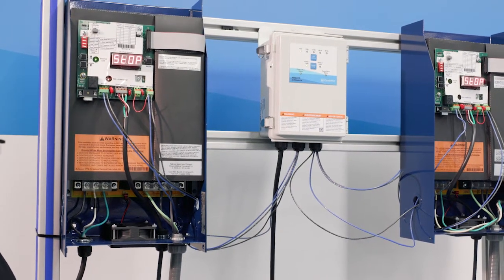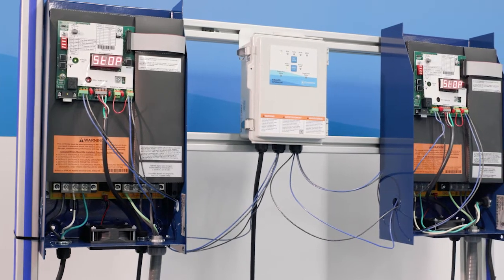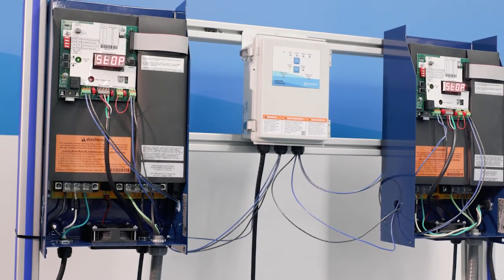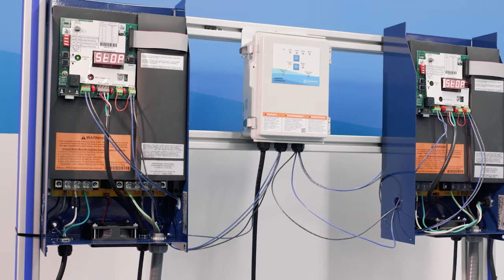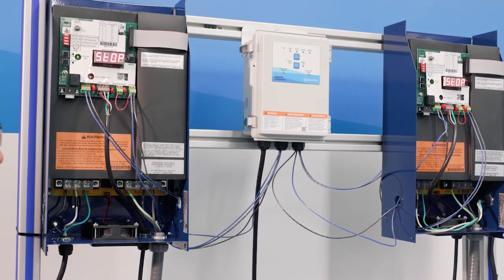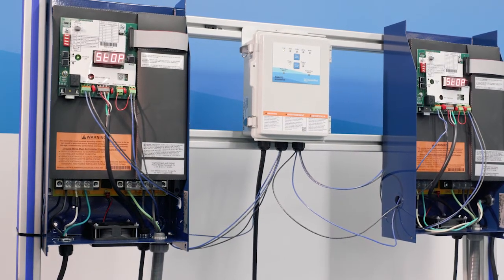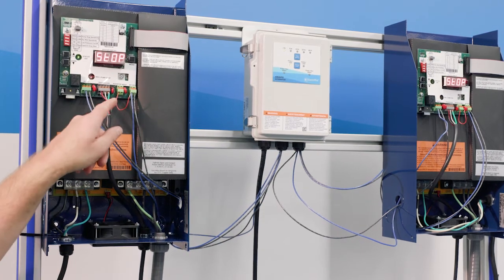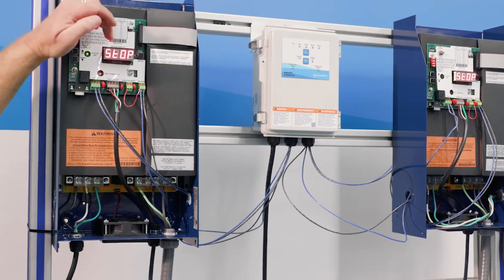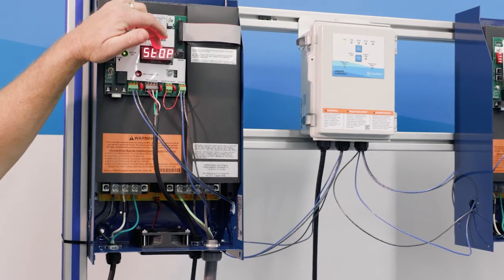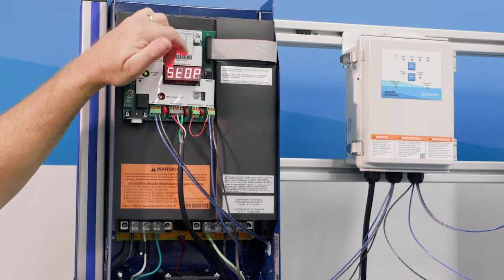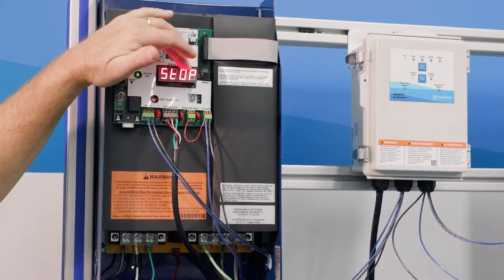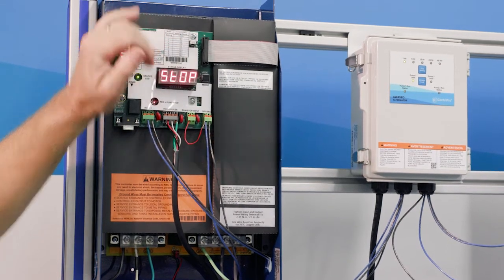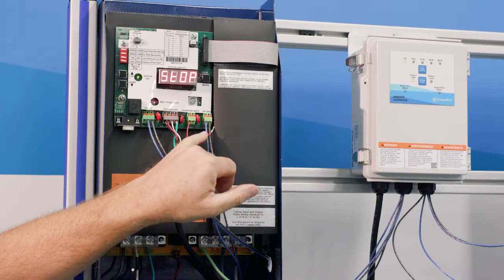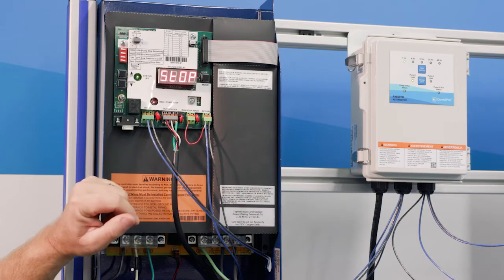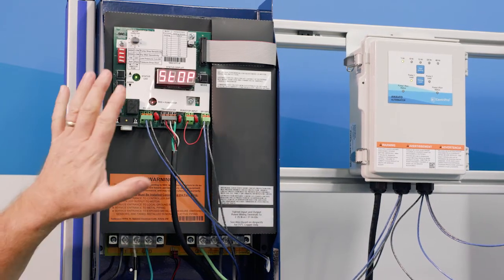We need to set the pressures up. And we basically need to set SP2, which is set pressure 2, and SP1, which is set pressure 1. So one of the tricks to do that is we got to have power to the box, right, to the drive. And so we can see we got power, we got the LED lit up, but it's not going to run because I pulled out the run stop input on both drives. So it is stopped right now.